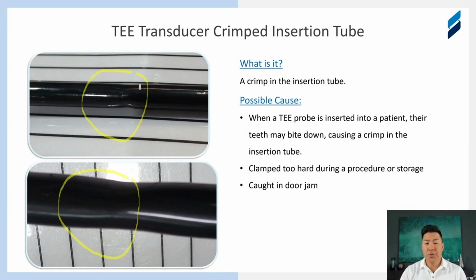Why is this an issue? Well, all the electronics and all the wires and all of the steering mechanisms are inside that. So they should be free to move. And now when you clamp it down, now you have tension, you have friction that wasn't supposed to be there. So wires can start to rub together and short. You have the articulation lines that are metal, and now they're really tight against each other, and now they're starting to rub against each other, and even against those wires. So you want to have this insertion tube corrected to prevent some pretty severe damage in the future.